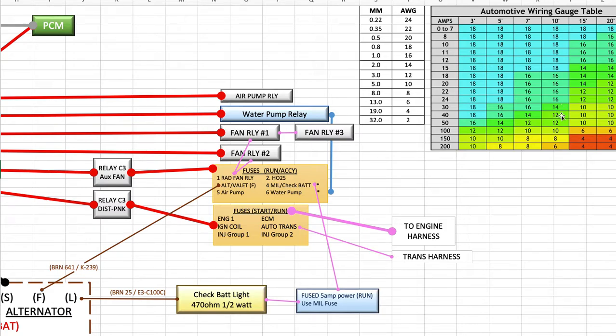But I always go, you know what, I'm going to go 12 gauge if I want to be sure. It also allows me to play with it a little more, maybe loop it around something I need to. But anyway, keep that in mind. So if I'm running a fuse and it's 5 feet, I go okay, 30 amp is 16 gauge. Let's say it was only a 10 amp fuse - I could go as little as 18 gauge, nice and thin, all the way across as long as I'm staying within the 5, 7, 10 foot range. Notice it goes all the way over here; once I get to 15, that's when I need to upgrade. So keep that in mind - that table is pretty helpful.